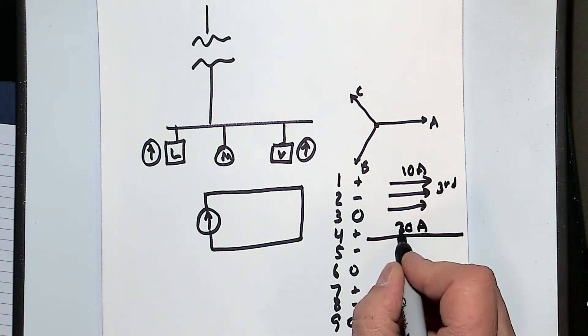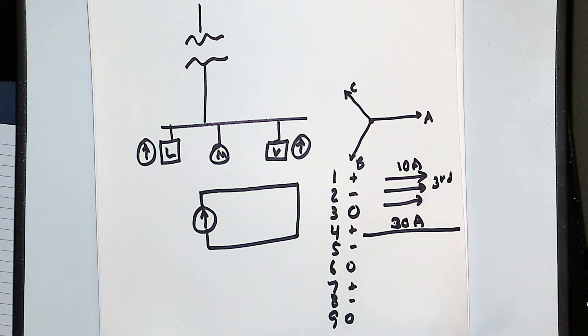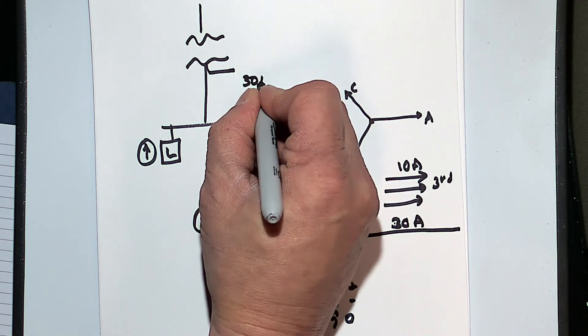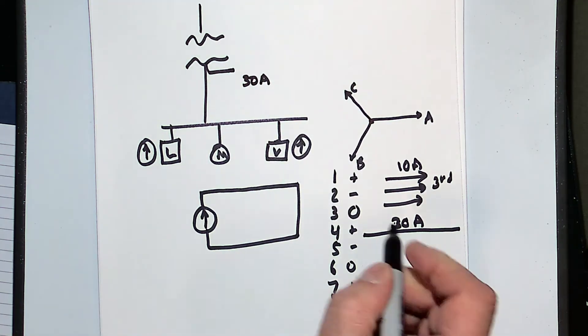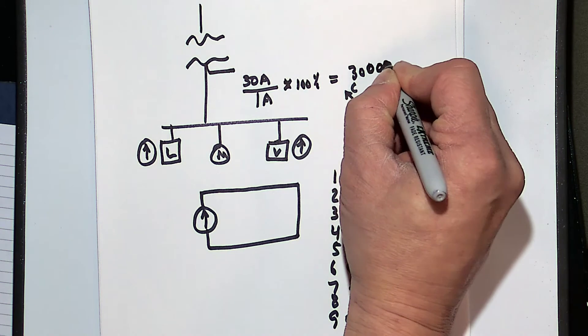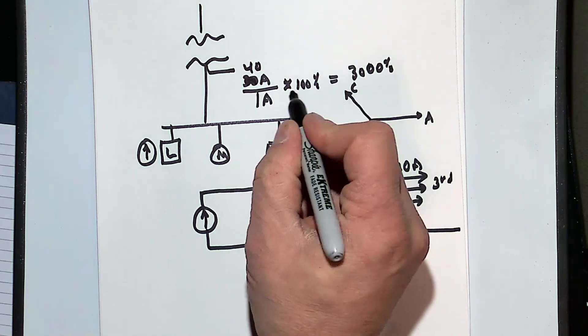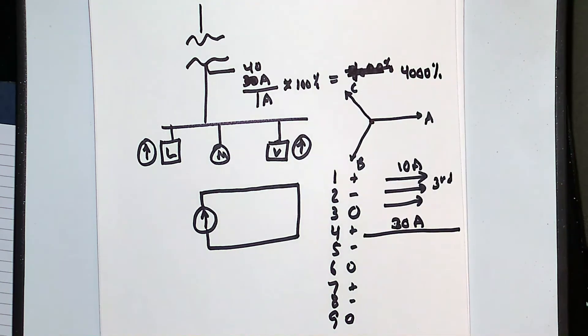That's why we oversize neutrals, as discussed elsewhere. But the point is, if I have 30 amps on my neutral and all of my other currents balance out — in other words, my 60 Hz current balances out — you can see how back here on my neutral I could get to 3,000 or 4,000 percent pretty easily. Say I have 30 amps of third harmonic current and one amp of 60 Hz current — that works out to 3,000% distortion. So to get to 4,000% distortion, all I would need is 40 amps of third harmonic current, and I would end up with 4,000% distortion on my neutral.